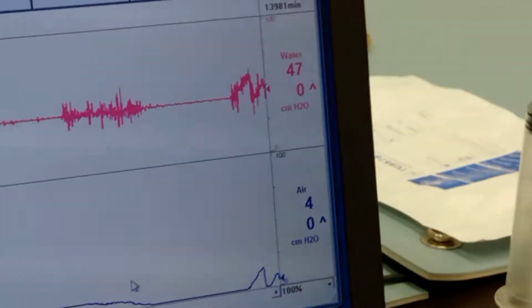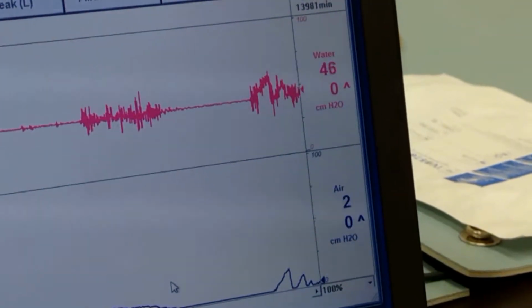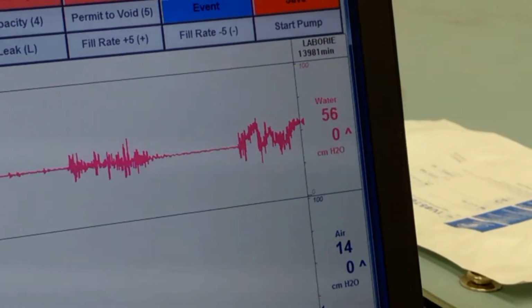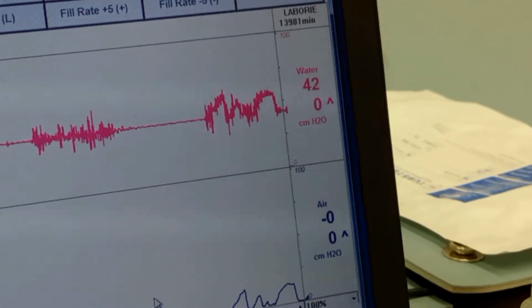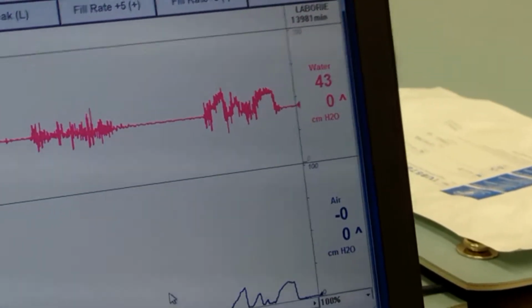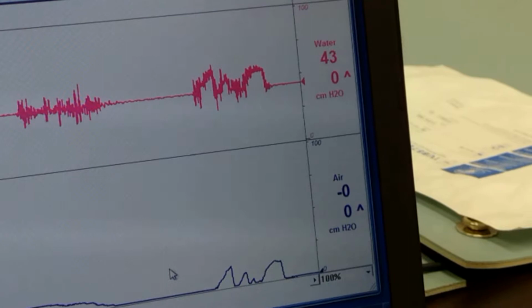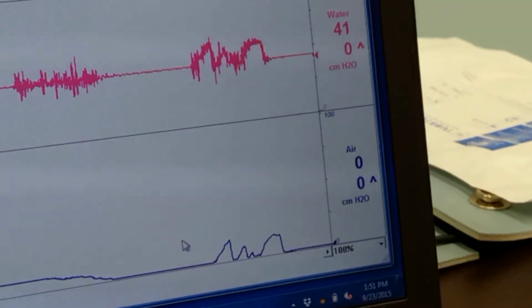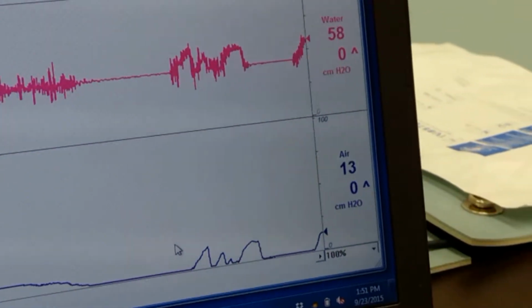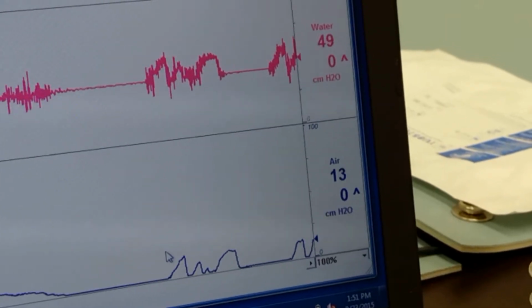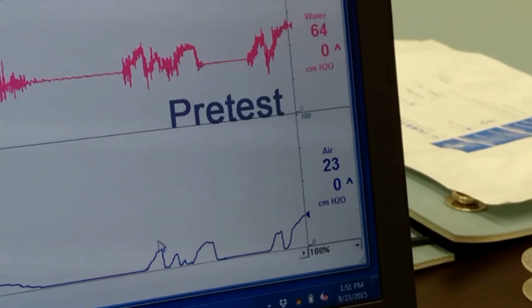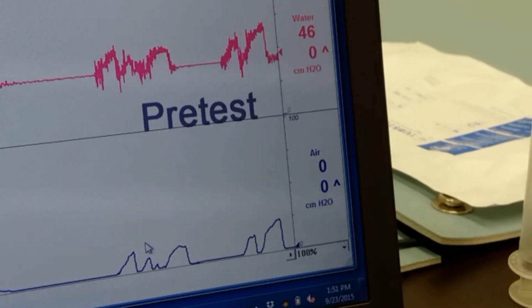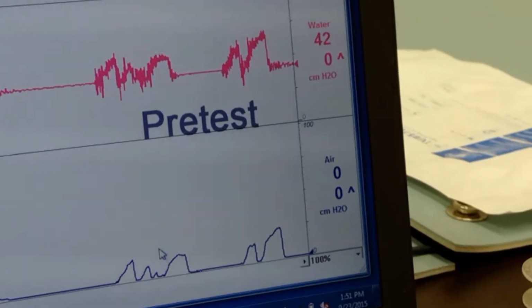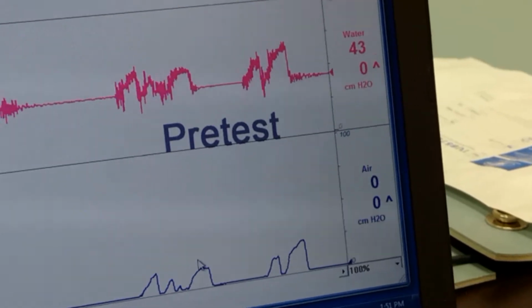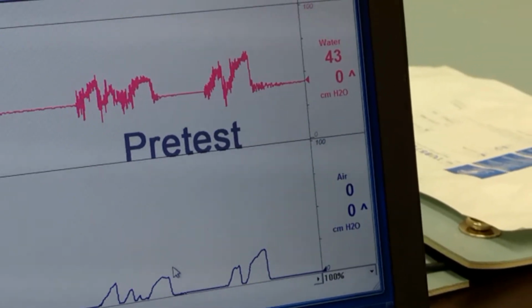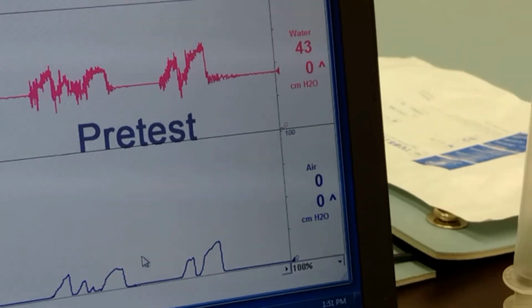So for individuals that are zeroing their catheters to the patient, that is why the shape of the bladder pressure curves are still identical, if not a little cleaner. You notice the air is so much smoother than the water up above. It's still going to be the same shape and same relative difference, and that's where air and water are clearly the same. But where they're different is because of these positional differences: the catheter position being critically important for the air, and the transducer position being critical for measurement with water.